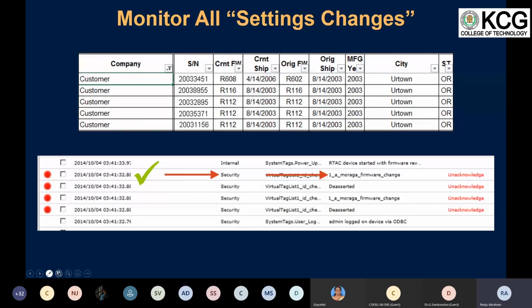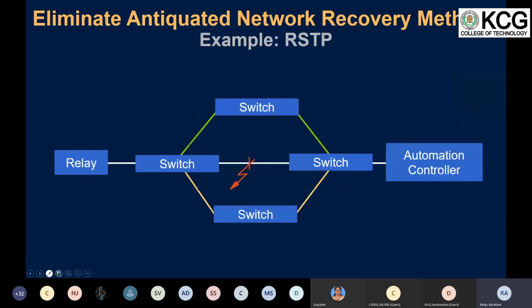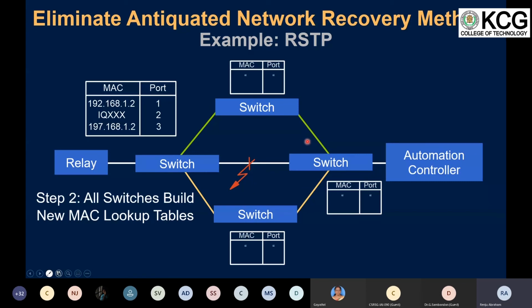The RSTP network, we must all be very familiar with this protocol. We should eliminate it in the OT network. In the OT environment, RSTP should be eliminated, because it could flood the network in case one side of the ring breaks. Here we can't create any third path. In a ring network, if one side fails, the other path will be there, but if the second path fails, there won't be any network connection. All switches build new MAC lookup tables every time one side of the network fails, which could cause delay in recovery of the ring.